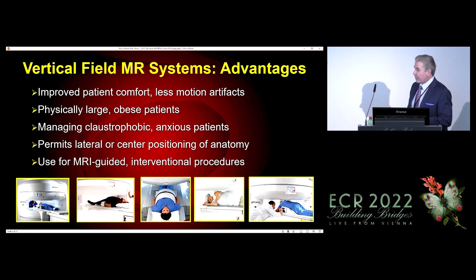Another advantage is that it permits lateral or central positioning of anatomies into the center part or the sweet zone for the MR imaging, which improves the image quality in many cases. And you have the ability to do MR-guided procedures or interventional procedures such as breast biopsies and neuro procedures, which can be driven, modulated and monitored directly with these MR-guided applications. So there's a lot of well-known and accepted advantages to scanning patients with a vertical field scanner.